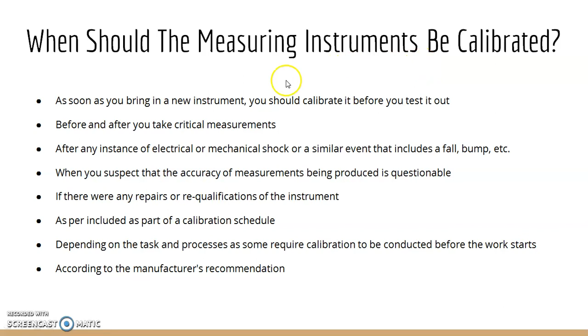Before and after you take critical measurements, sometimes it is very crucial. After any instance of electrical or mechanical shock that may happen during transport or any similar event that includes a fall or a bump, etc. When you suspect that the accuracy of the measurements being produced is questionable, if there were any repairs or requalifications of the instrument, then calibration is a must. As included as a part of the calibration schedule, as per schedule we need to calibrate them. Depending on the task and process, some require calibration to be conducted before any work starts, and according to the manufacturer's recommendation, if they recommend to calibrate now and then, we should calibrate. These are the times when the measuring instrument should be calibrated.